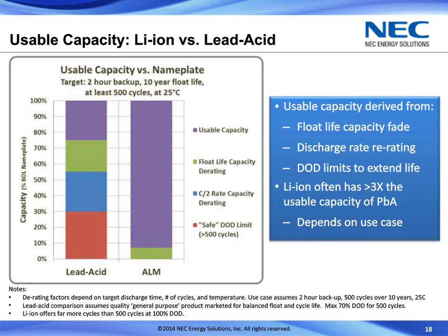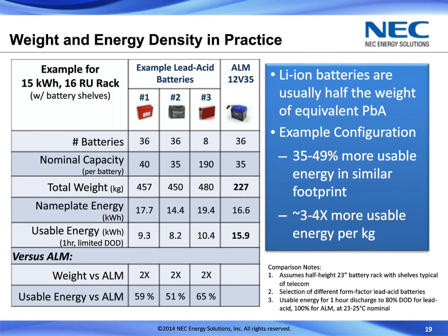The other factor is weight and energy density. We talked about this with that graph. Briefly, this is an example where we took 3 different types of lead-acid batteries, and we imagined, gee, if I have half the height of a telecom rack, and I populated it with a bunch of batteries as close together as I could, what kind of energy density could I get? Well, we can fit different types of batteries, different sizes. We're comparing 3 different lead-acid batteries here with our ALM 12V35 as an example of a lithium-ion battery.